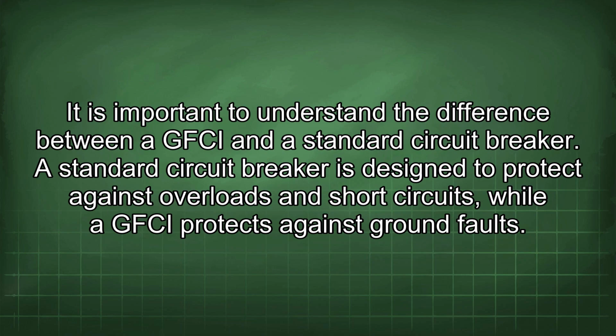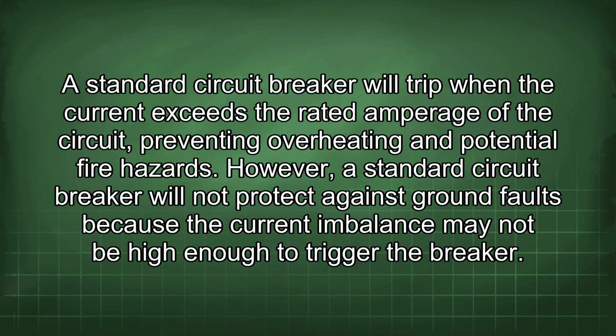It is important to understand the difference between a GFCI and a standard circuit breaker. A standard circuit breaker is designed to protect against overloads and short circuits, while a GFCI protects against ground faults. A standard circuit breaker will trip when the current exceeds the rated amperage of the circuit, preventing overheating and potential fire hazards. However, a standard circuit breaker will not protect against ground faults because the current imbalance may not be high enough to trigger the breaker.